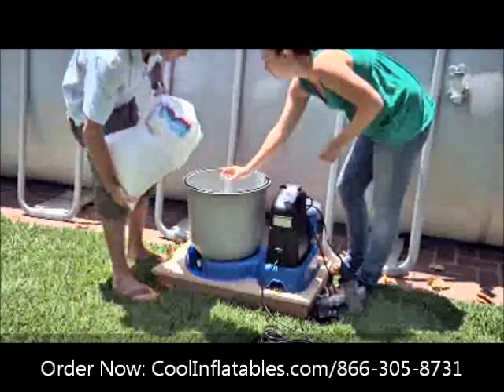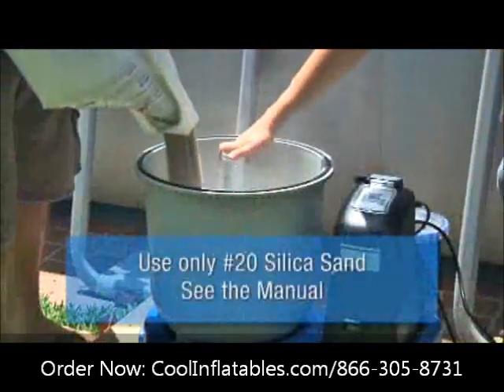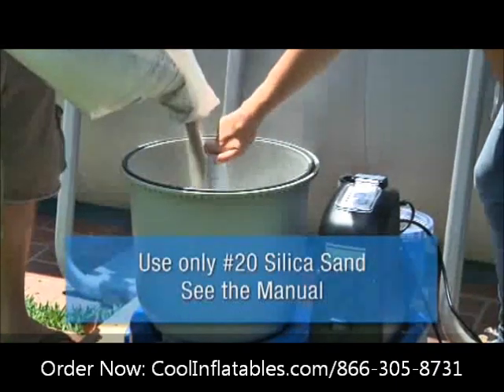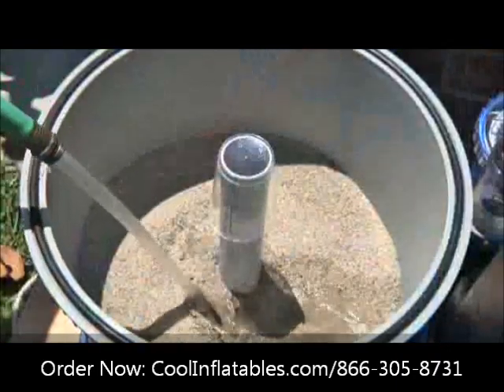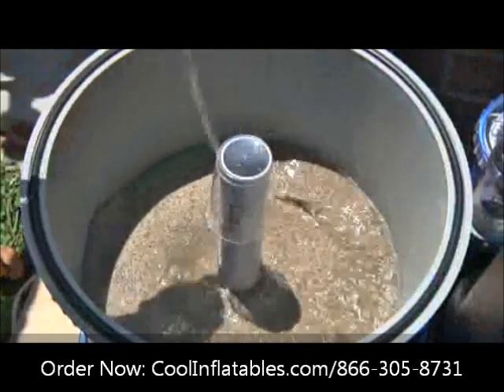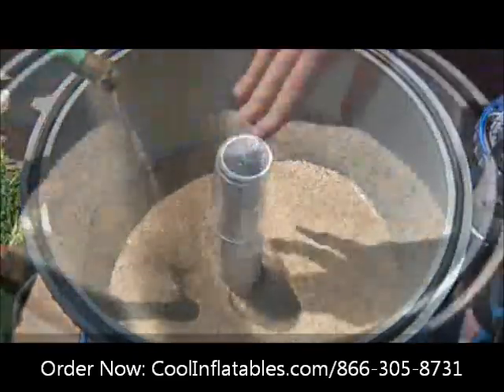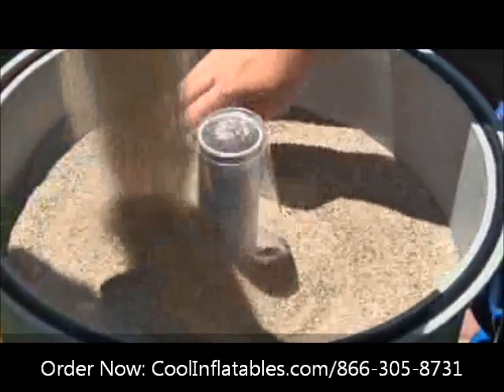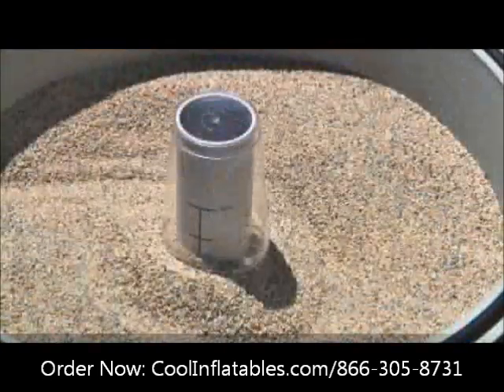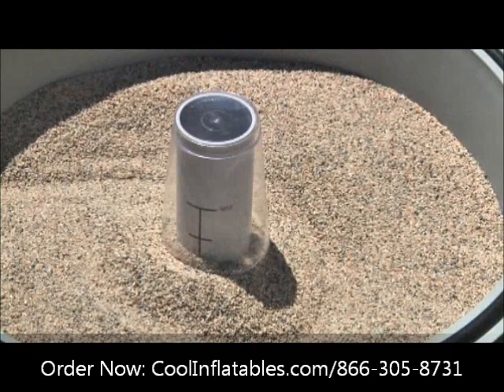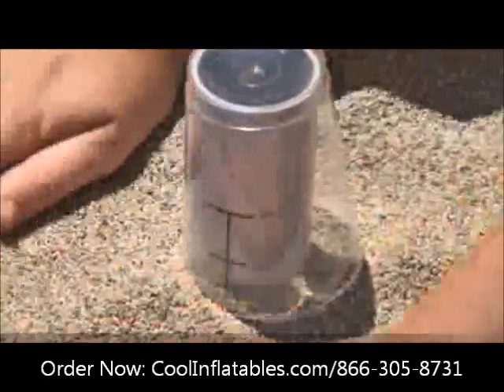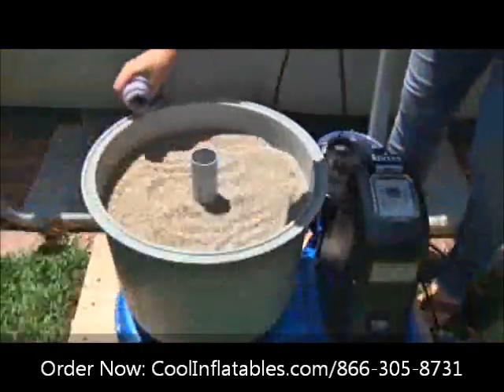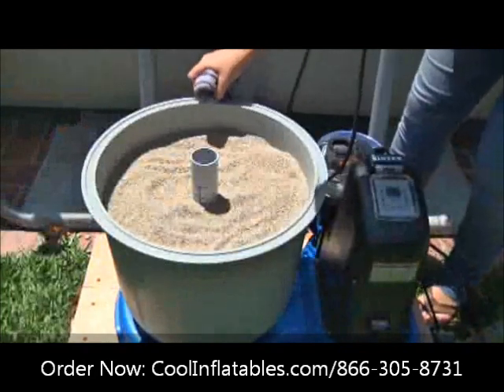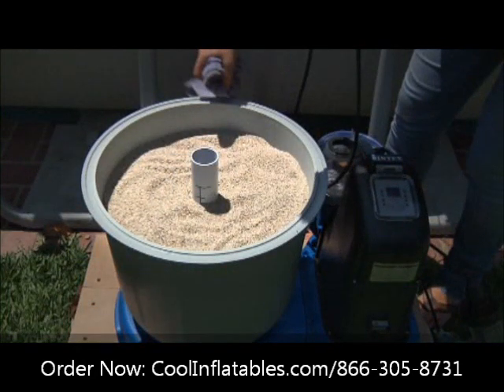While one person holds the center pipe straight, half of the sand can be slowly poured into the tank. Add water to the tank until it just covers the sand as a cushion when the rest of the sand is poured. Add more sand until the level is between the minimum and maximum marks on the center pipe. Spread the sand out evenly by hand. Remove the protective cover from the pipe and wash any sand from the top edge of the tank. Check to make sure the center pipe is still centered in the tank so the valve cover will fit.